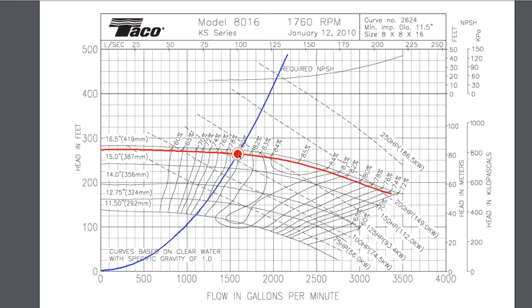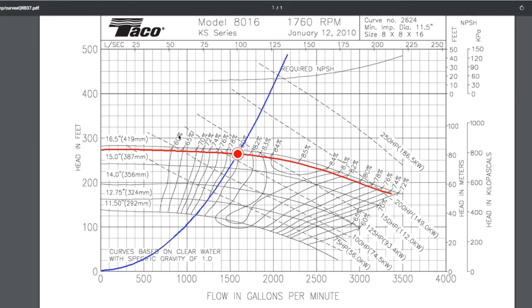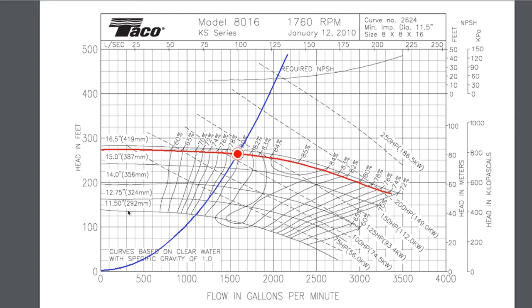The red point is our operating point. Looking at the rated curves, we can take the same model 8016 pump and put different sized impellers in it. The bigger the impeller diameter, the more flow you get for a given head, or the more head at a given flow. So we can choose between 16.5 inch, 15 inch, 14 inch impellers, and so on, each giving different head-flow performance.